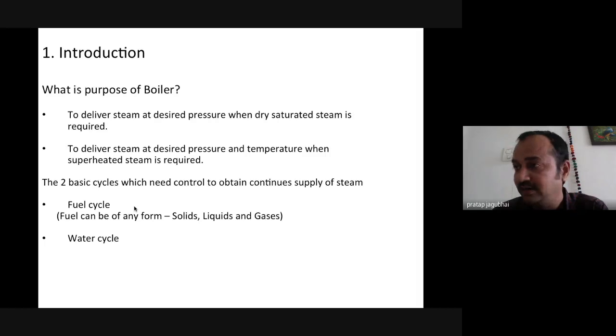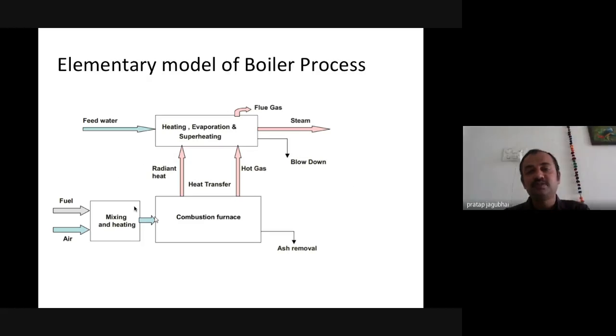In the boiler, as we see in the complex GA, it is basically divided into two categories of cycles. One is the water cycle, the water and steam drum combination together, and the other is the fuel cycle. The fuel cycle is the fuel, air, draft, and chimney all put together. In the fuel cycle, any kind of fuel can be fired, liquid, gaseous, or solid, which we'll discuss in more detail. An elementary model will give you more idea about how the boiler actually works inside, from an elementary point of view.